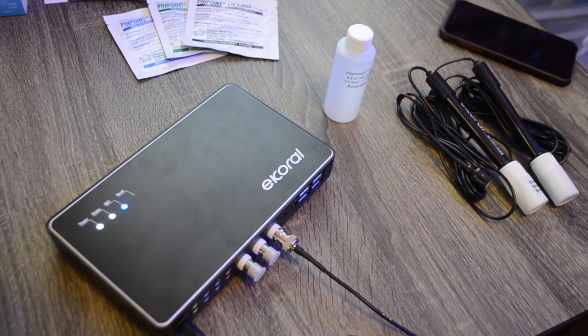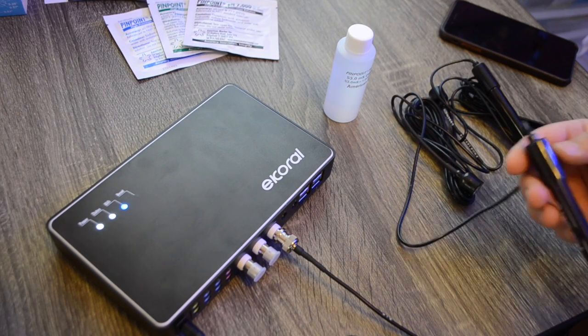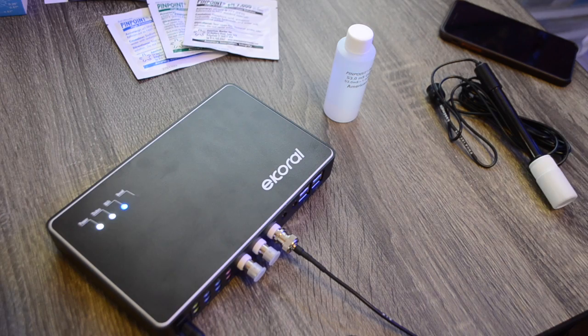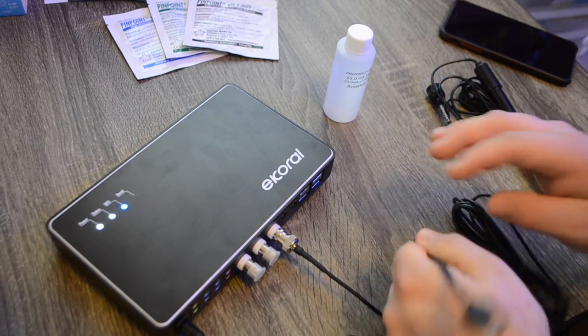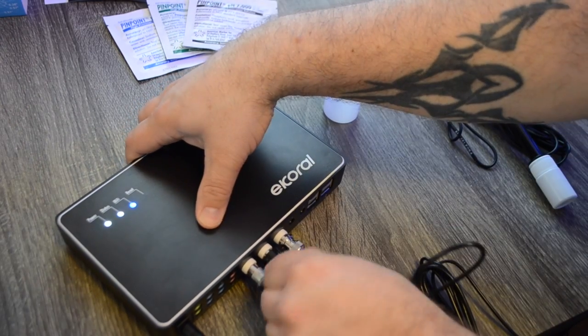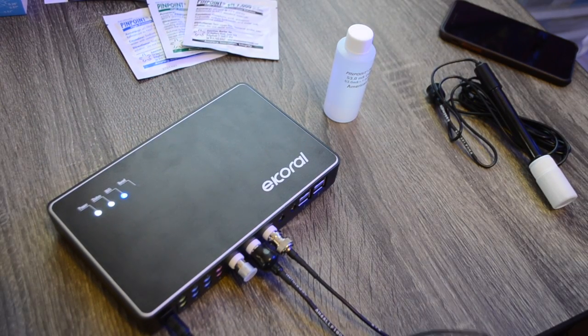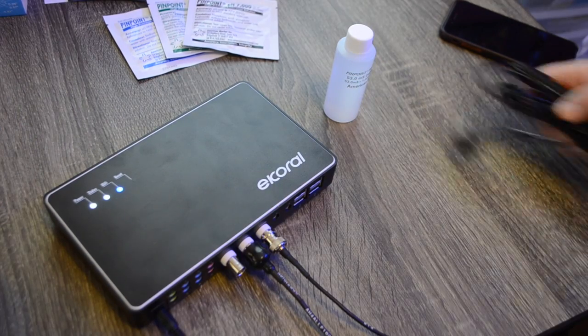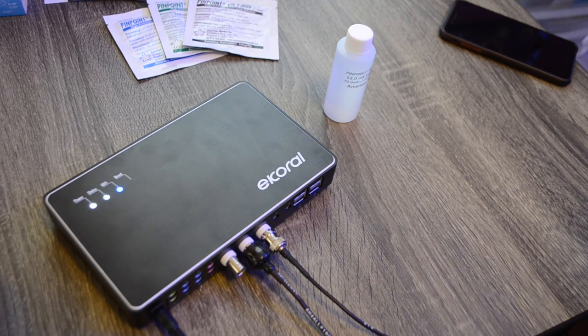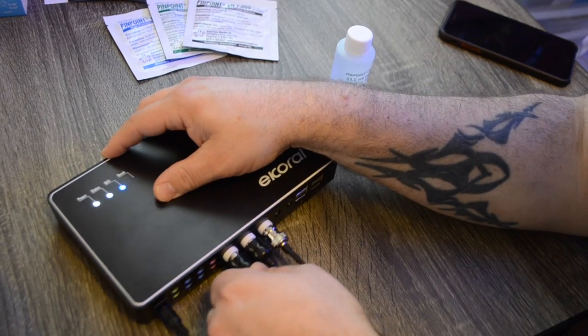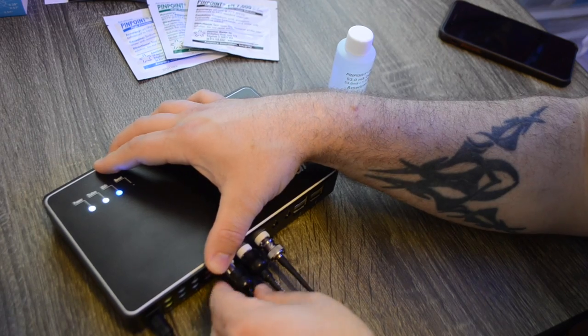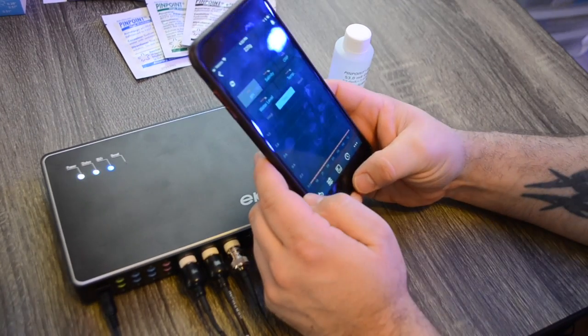One thing that I absolutely love here is that they tell you the last time that you calibrated your probe. Now, if you go back to your settings screen on your eKoral app, there just below the calibration section is alerts. What I would like to see in the future is that you can take that last time that your probe was calibrated and create an alert or a notification or something to notify you when you need to recalibrate your probes.